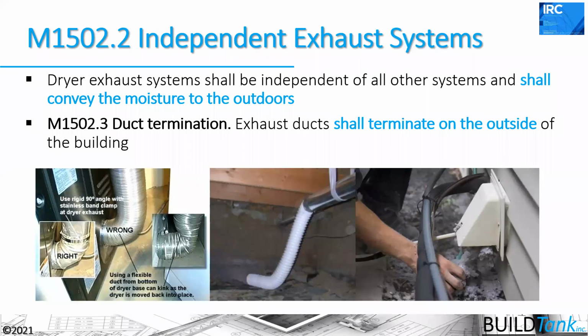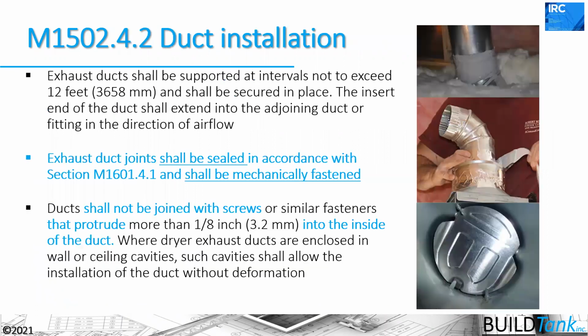Same with laundry vents, though. They have to be ducted all the way to the outdoors and shall terminate to the outside here. And we're really talking about installation of these duct systems that are ducted to the outside. They should be sealed and made airtight, just like any other HVAC duct there. So taped or ideally mastic there. And then we want to install them so that they actually function. In this case, you see the picture in the lower right-hand corner. The screw that's connecting the duct is impeding the ability for this damper to work. So it's actually not going to work.